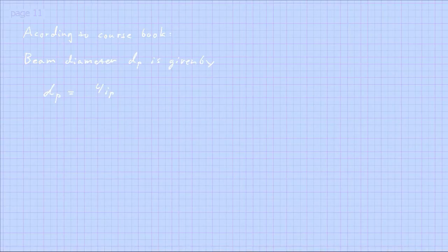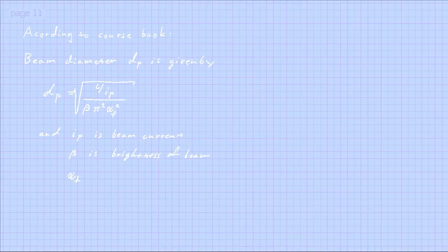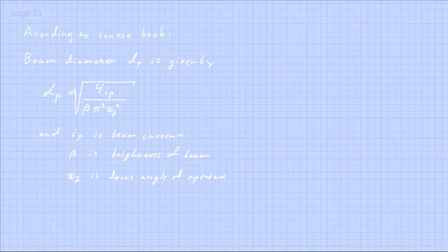Probe size and current of the beam. You can change the spot size of the beam in an electron microscope, and a few parameters affect this. In the course book you can see an equation that relates to this: the beam diameter dp is proportional to the square root of the beam current divided by the brightness beta of the source times pi squared and the aperture angle in focus squared.